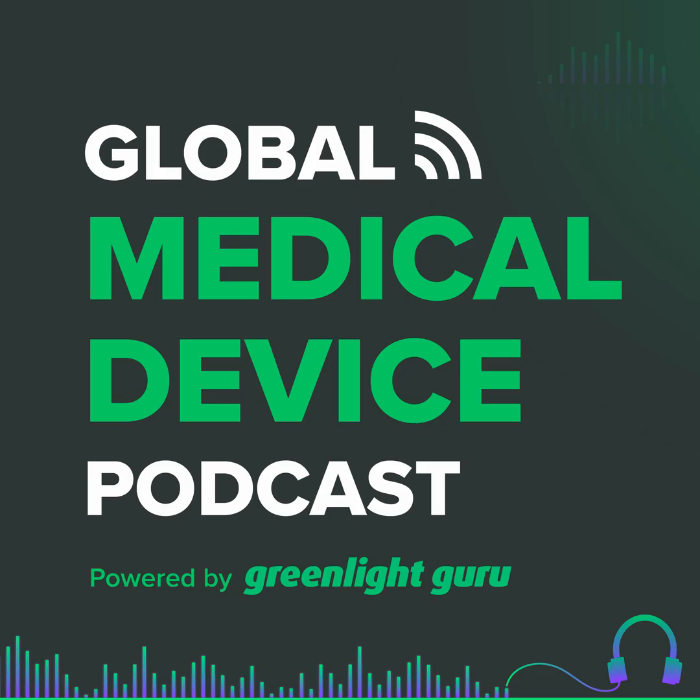So what do you think are the most beneficial uses for this? As with everything, there are advantages and disadvantages. Theoretically, a PCCP will allow faster label expansions and getting modified devices quicker to the market with minimal or no FDA involvement. But remember, Eddie, the first word I used there was theoretically, because in the PCCP, as we've talked about before, you still have to include the methodology to support that change. You still have to include the data. So that's going to take time and money to collect.